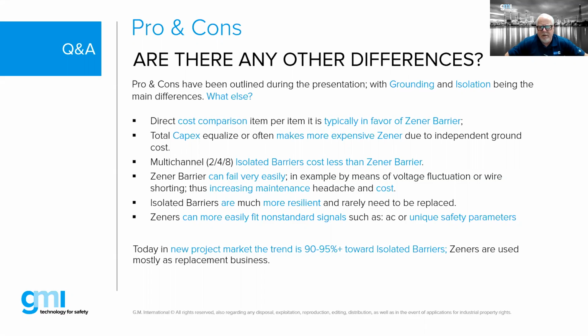Well, one thing that's not on this slide, Paulo, and I think this is an important consideration - generally, as we talked about with galvanically isolated barriers, we have to introduce a transformer on the inside of a barrier, right? So generally speaking, the first generation galvanically isolated barriers were much wider. As a matter of fact, the first generation GMI products were about 25 mil, I believe. So the next generation, manufacturers have been able to make their galvanically isolated barriers much thinner. And so the stacking density, where Zener barriers used to have a big advantage, has somewhat gone away, because galvanically isolated products now have shrunk significantly in thickness and density for DIN rail mounting.